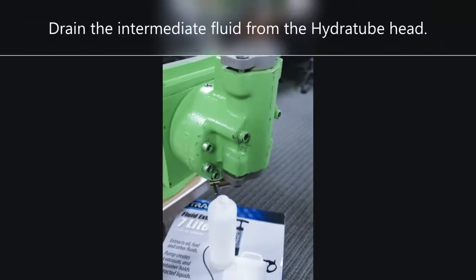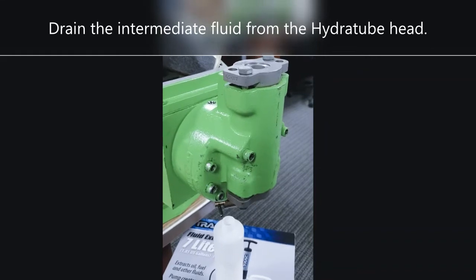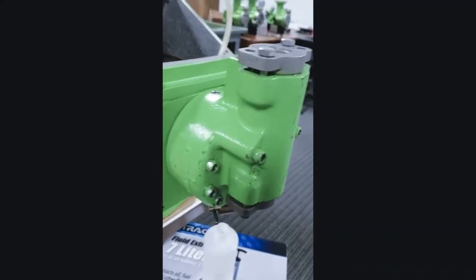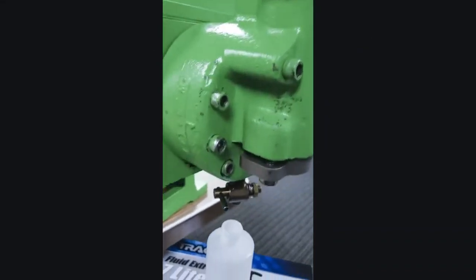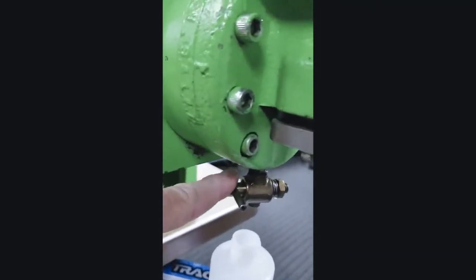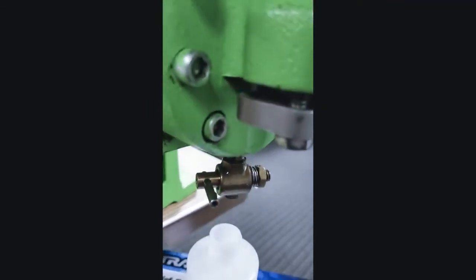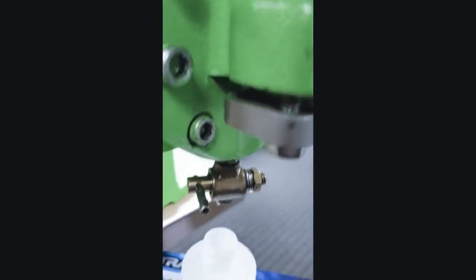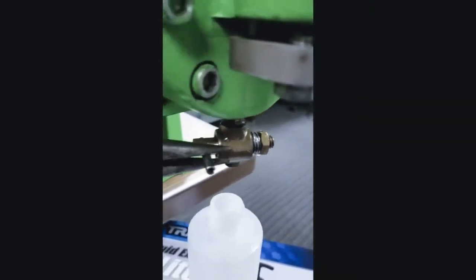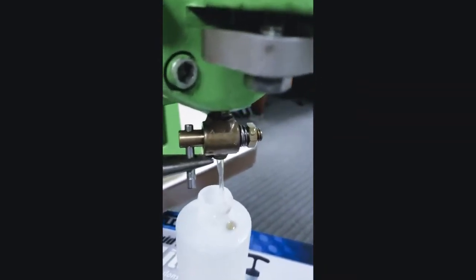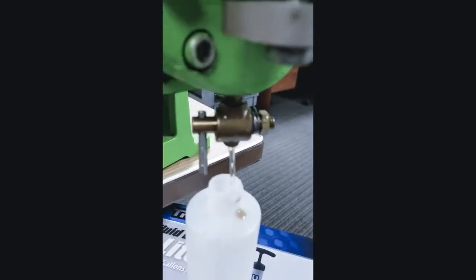The next step is going to be to drain the intermediate fluid out of the Hydratube head. On a typical pump on the bottom, you will have a plug which will screw into the bottom of the Hydratube head. In the case of our show pump, we've installed a valve for testing and for show purposes. So what I'm going to do now is open this valve and drain out that fluid that's been in the Hydratube head.